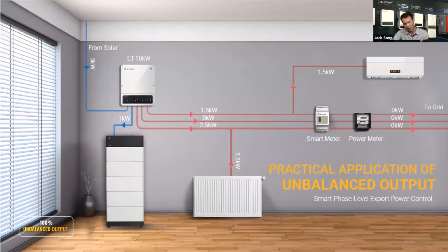Like in the first picture, I introduced the balanced outputs. A balanced output system cannot be used in Spain, because the output of the inverter has to exchange with the grid. One phase buys power from the grid and another phase exports to the grid. This is not allowed in Spain, and also in many other places like the Czech Republic and some places in Germany. In the future, maybe it will change in Italy and other European countries, such as North European countries.